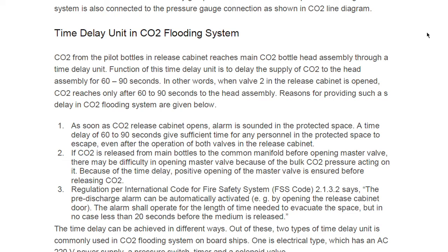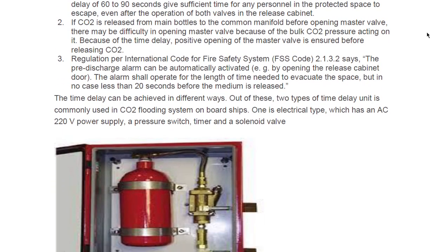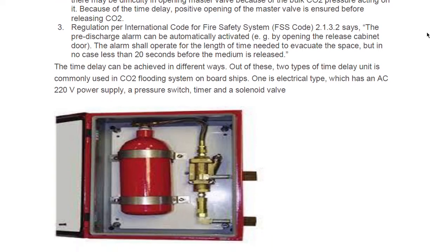If CO2 is released from the main bottles to the common manifold, before opening the master valve, there may be difficulty in opening the master valve because of bulk CO2 pressure acting on it. Because of the time delay, positive opening of the master valve is ensured. The time delay can be achieved in different ways. Two types of time delay units are commonly used in CO2 flooding systems on board ships. One is the electrical type, which has an AC 220-volt supply, a pressure switch timer, and a solenoid valve.